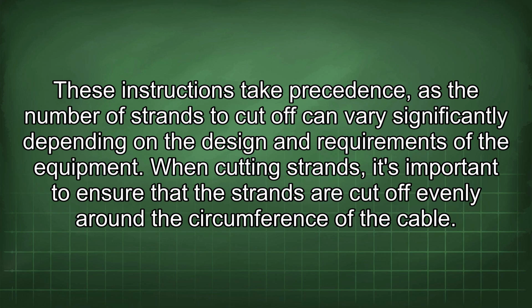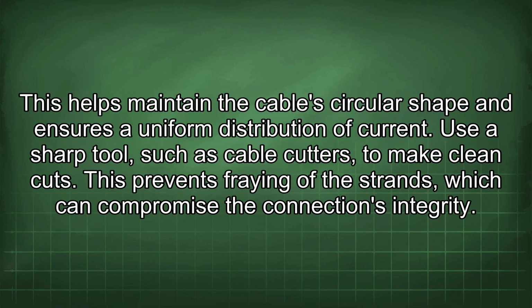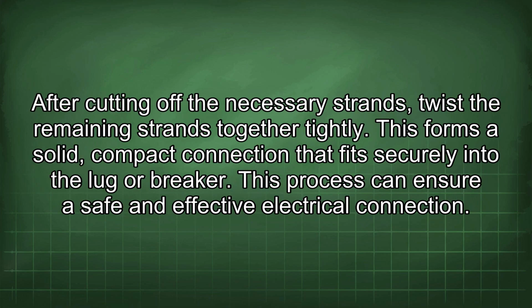requirements of the equipment. When cutting strands, it's important to ensure that the strands are cut off evenly around the circumference of the cable. This helps maintain the cable's circular shape and ensures a uniform distribution of current. Use a sharp tool such as cable cutters to make clean cuts. This prevents fraying of the strands, which can compromise the connection's integrity. After cutting off the necessary strands, twist the remaining strands together tightly. This forms a solid, compact connection that fits securely into the lug or breaker. This process can ensure a safe and effective electrical connection.